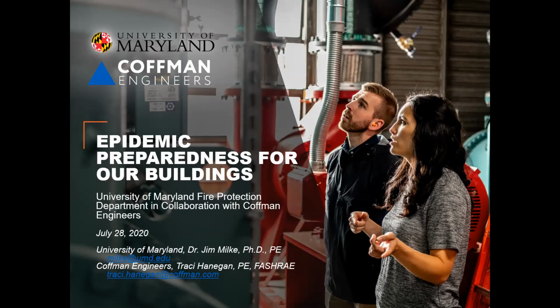So with this discussion of filters, what about maintenance workers and any protection needed when they go in to do maintenance or filter replacements? Absolutely. The ASHRAE Epidemic Task Force addressed that. There's a section called Filtration and Disinfection with specifics you can look at, but the quick summary is: definitely wear personal protective gear. Put on a mask, wear gloves, and coveralls if you have them, like Tyvek booties. At least mask and gloves, and try to shut the air handling unit down when you go to change filters. I know some people walk into air handlers while they're still running, and in some cases that's just how it has to be, but it's best if the air handler can be shut down.